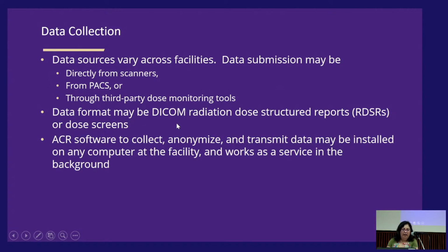The data format has to be DICOM. It makes sense. I mean, as our scanners are getting more modern across the United States, most facilities will send the DICOM radiation dose structured report. But some sites still, rural areas, might have a 4-slice scanner, or even a 16-slice, which may not have a DICOM structured dose report, because you have to buy that as an option in many cases. So that can be sent, but that's going away. ACR is going to not take that anymore in the near future.